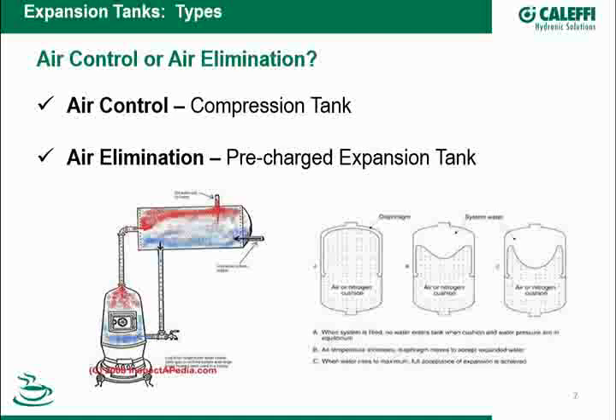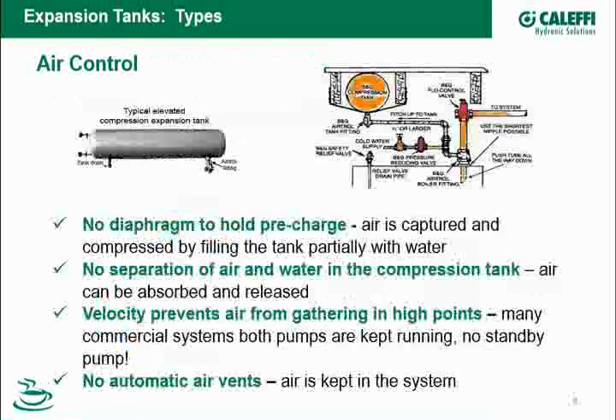Okay. So if I do air control, I'm going to do what's called a compression tank. I have a picture on the slide. There's a picture of a typical compression tank off to the left-hand side on the top. You also hear these referred to as plain steel tanks. There's no diaphragm in there. What you have is a plain steel tank with a fitting on the bottom. You see this air control fitting on the right-hand side of the tank, and then there's a gauge glass shown here. Okay? Now, why is it called a compression tank? There is no pre-charge in the tank itself. It's just a steel tank. So when the system is filled, air is captured in this tank, and pressure is generated by compressing the air in the tank itself. The end result is part of the tank's volume is always going to be filled, maintaining the charge on the tank.